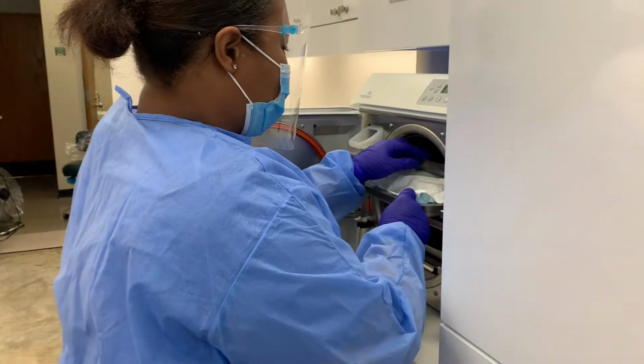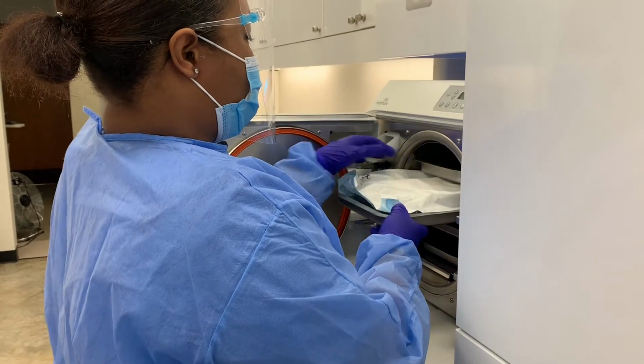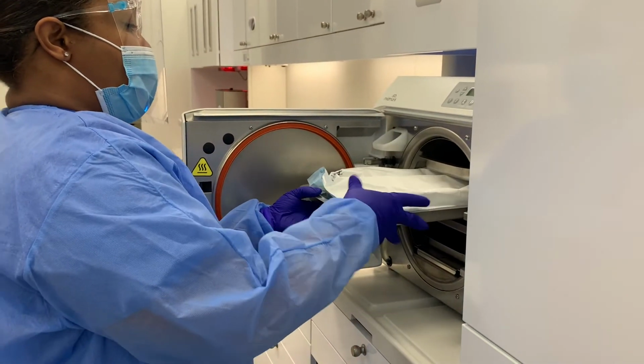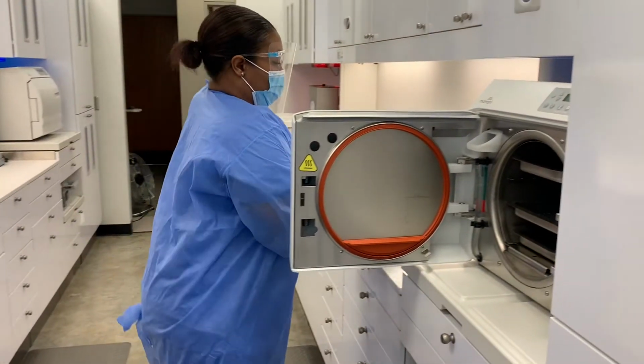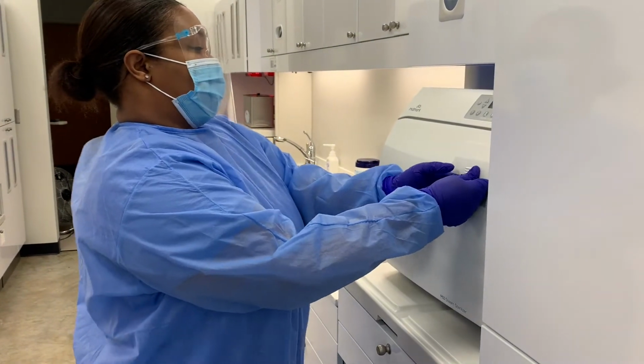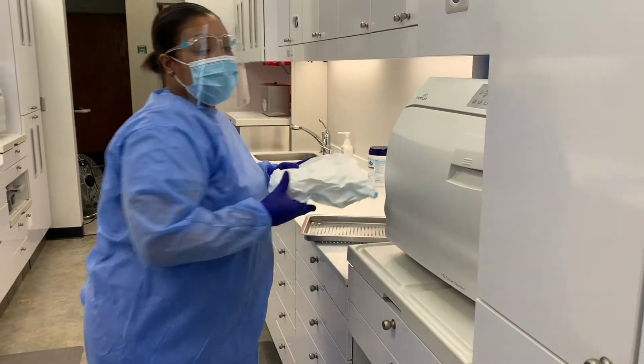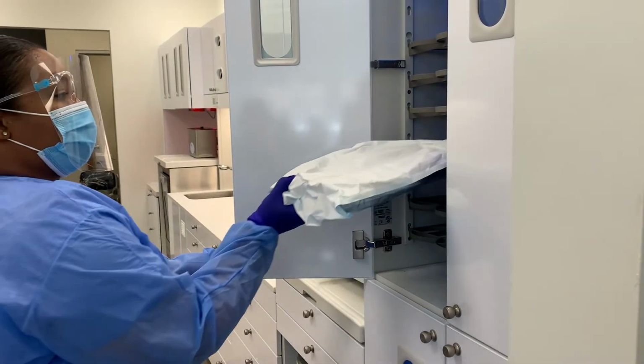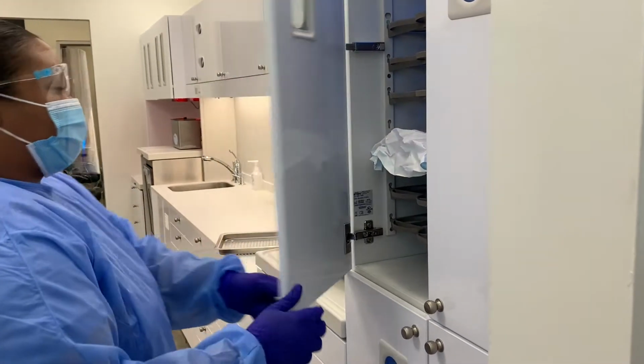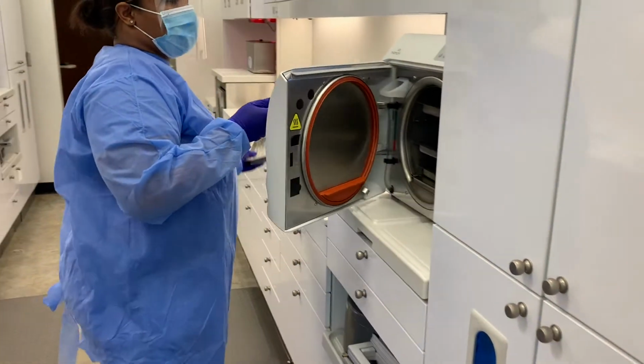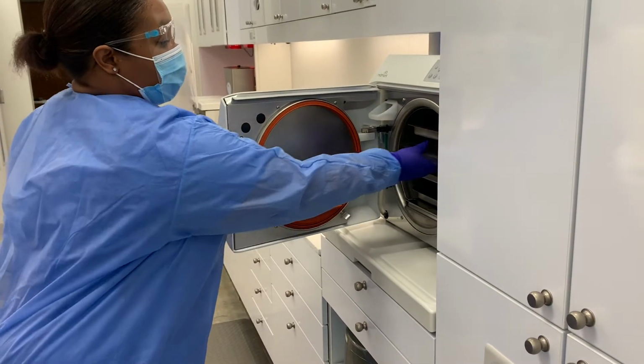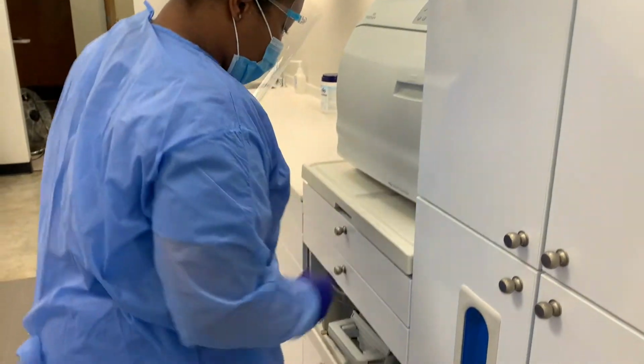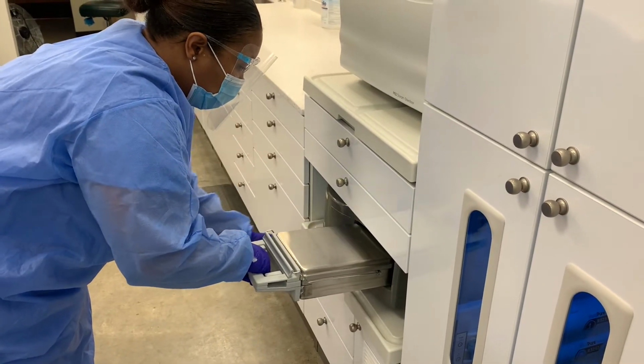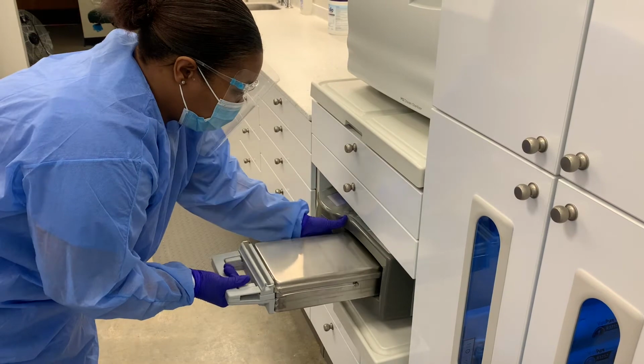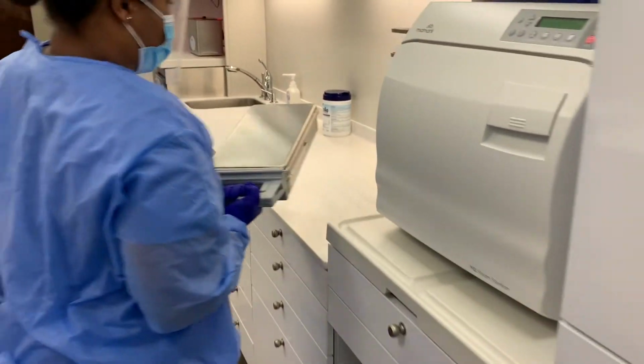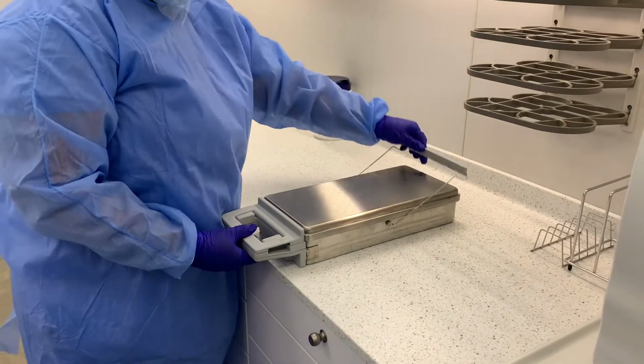The autoclave door will pop open when the cycle has reached the end. Be sure to stand back as the steam is very hot. When it is ready to open, pull the handle up and out. When retrieving from the Statim, try to only grab the drawer by the handle as it is also very hot. All cassettes and instrument packages are placed in designated areas for storage, to be returned to the treatment room.